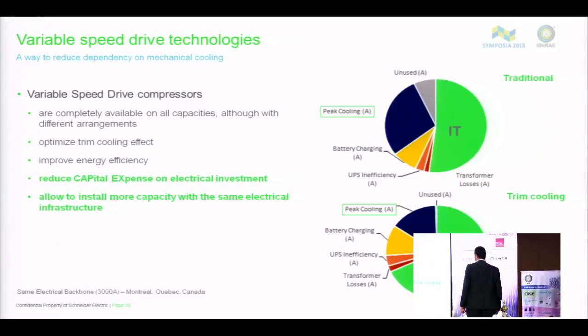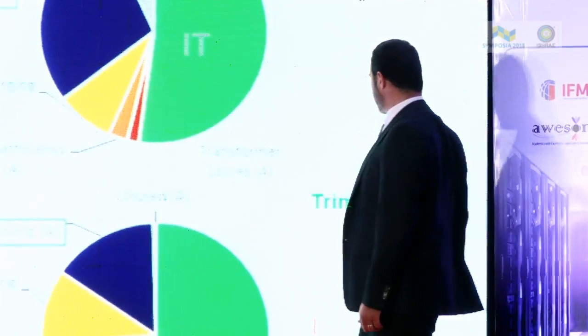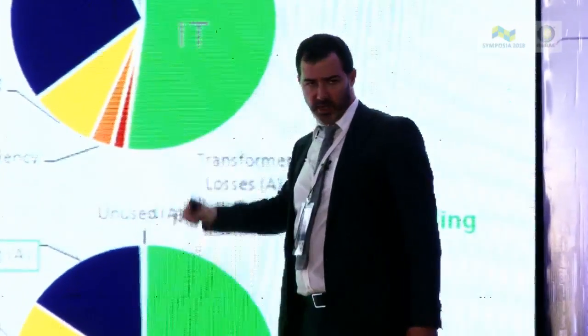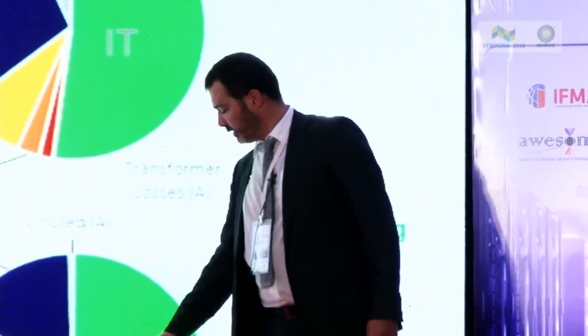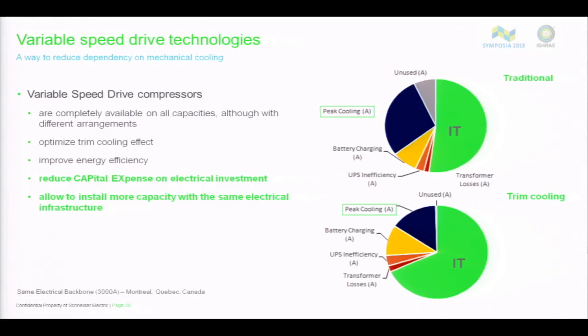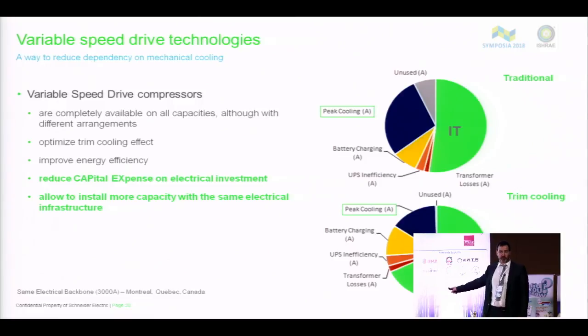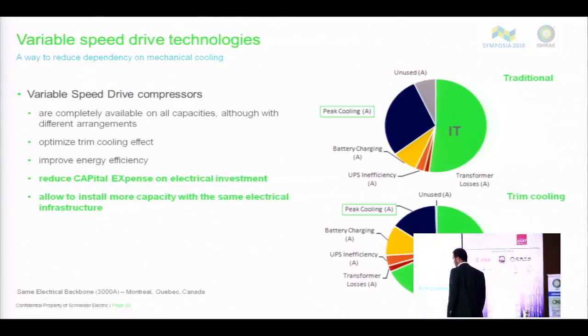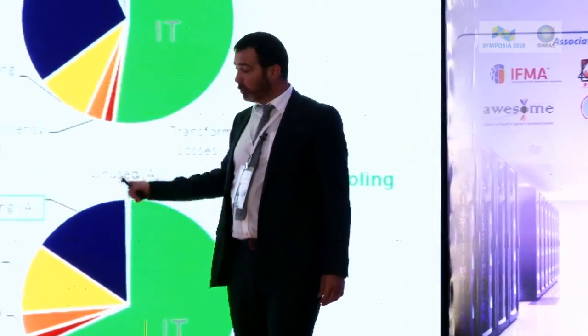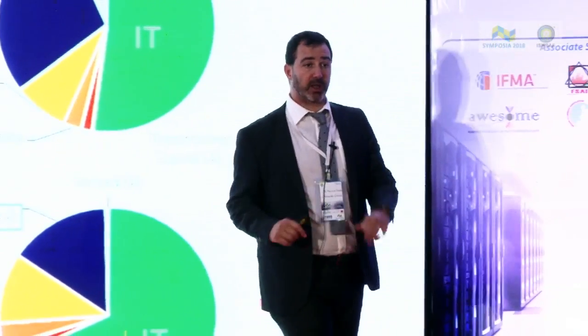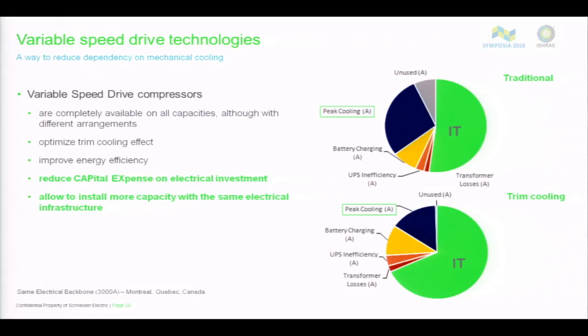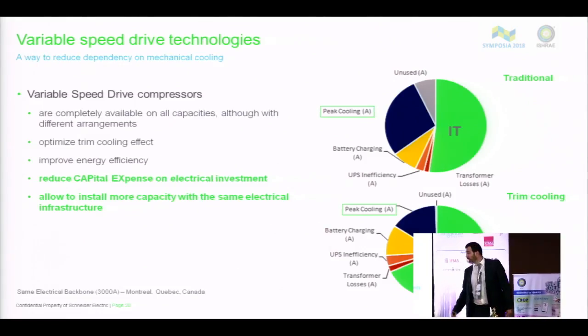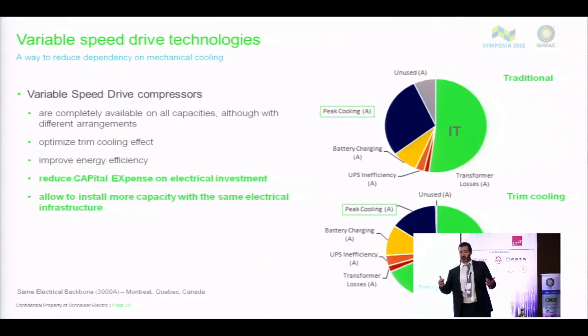So if we consider a traditional approach or a trim cooling approach, so an approach where the compressor covers only a portion of the capacity with an inverter, assuming the same design in terms of amperage, there is much more amperage for the infrastructure. You have two choices: use this, if the customer is a co-locator, to sell more amperage to the customer, so to have more racks, or downsize the electrical infrastructure and have more savings on the capital expense. So it is a balance that you can do. There is an 8% saving on the capex or a plus 15% more power to sell to the customer. It's a choice of business.